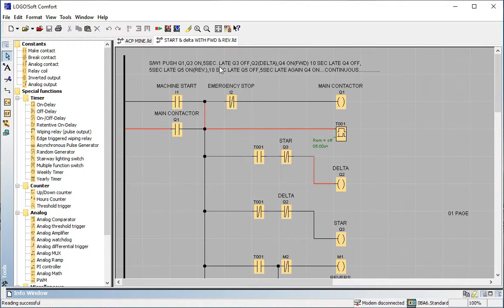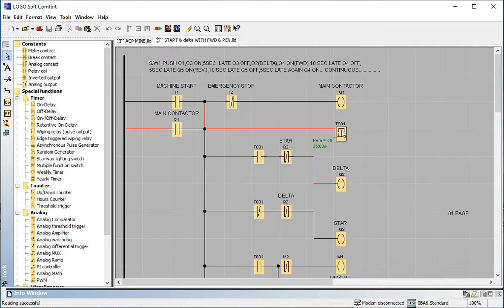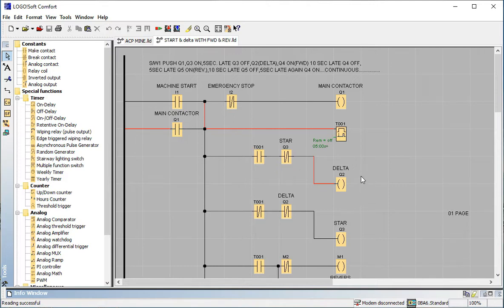We first start in star, then convert to delta, because delta provides maximum speed for a 440V three-phase line connection. As I described in my previous video, Q1 is the magnetic contactor — when Q1 is on, Q3 (star) comes on. The timer is connected; when five seconds are counted, Q3's NC contact becomes NO, meaning Q3 (star) turns off, and Q2 (delta) turns on.